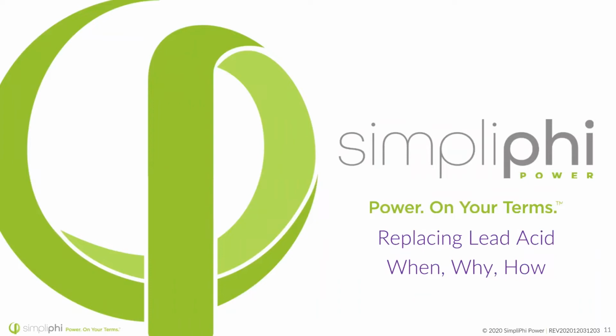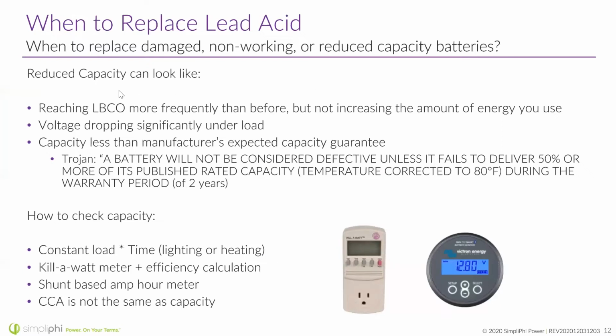So moving on from troubleshooting, I want to talk a little bit about how, when, and why to replace your lead acid bank. So if those troubleshooting steps did not solve your problem, here is what will. So when should you replace your batteries? Well, maybe they have a reduced capacity. This will look like reaching low battery cutout and having your inverter disconnect more frequently than before without increasing the amount of energy that you use from your batteries.